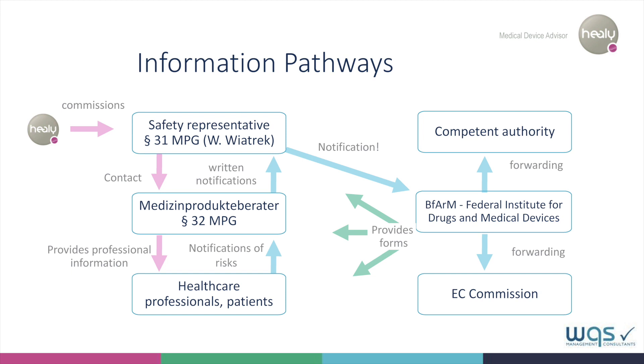What is the information path in the event of damage? Healy GmbH officially appoints a safety representative, who is in direct contact with all medical device advisors who inform the customer about the product. In the case of an incident with the medical device, the user informs the medical device advisor, who in turn immediately informs the safety representative in writing. The safety representative then evaluates the incoming report and, if a safety risk actually exists, reports the incident to the Federal Institute for Drugs and Medical Devices, which forwards the incident report to the relevant authority and the EC Commission and provides the necessary forms for further processing to all parties involved.